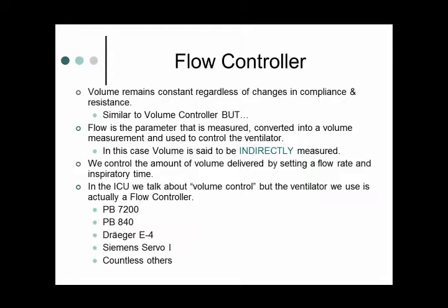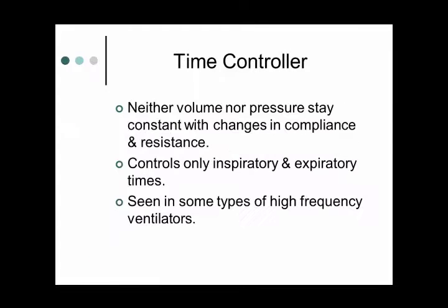Can we have it in a lab to see? I can show you a piston-based ventilator, sure, or a bellows-based ventilator. You won't see anything different. They all deliver gas to the patient, but how it's delivered is different. The last one is a time controller, and we're really just controlling inspiratory and expiratory times. For right now, we're not going to encounter them at all. High-frequency ventilation is an example of this, but I'm not even touching that one. Mary can touch it.